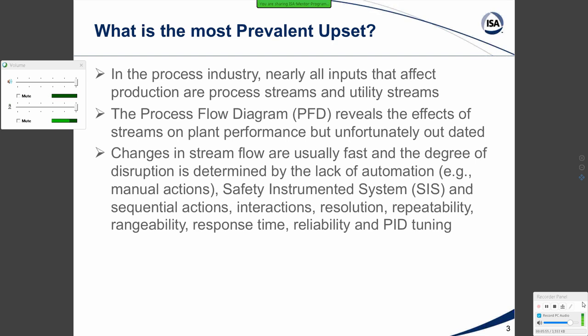And then in particular with flow measurements, we have a problem with rangeability, where as you get down to low flows, the signal can get very erratic. And the best thing we do in some cases, like with vortex meters, is actually drop out the signal.